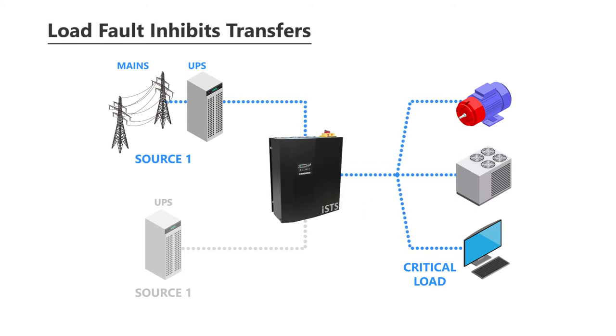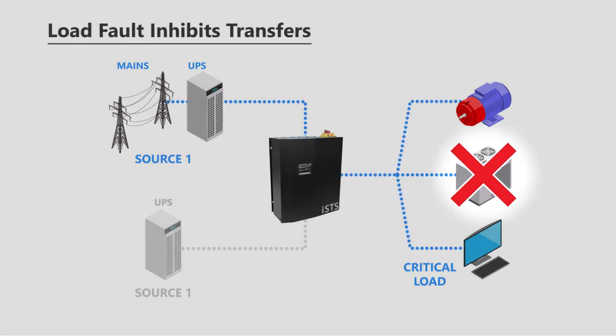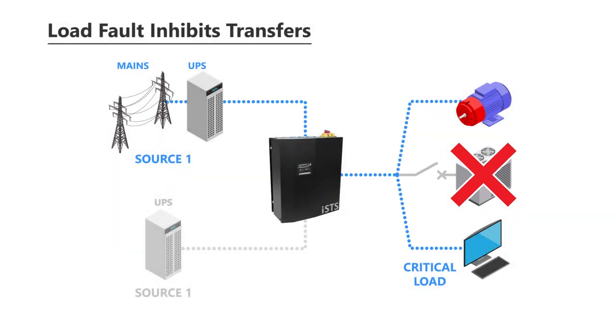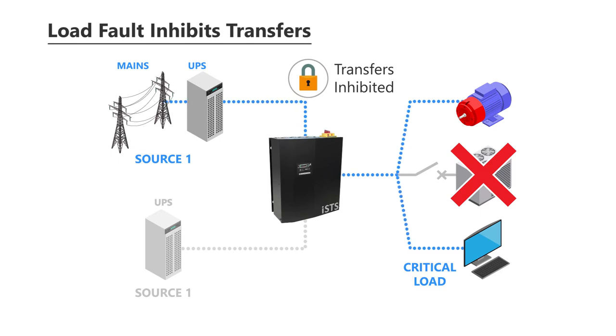In the case of a load fault, the STS will inhibit transfers until the connected equipment clears the fault. Inhibiting transfers prevents a load fault from affecting both sources, which otherwise would result in a total power system failure.